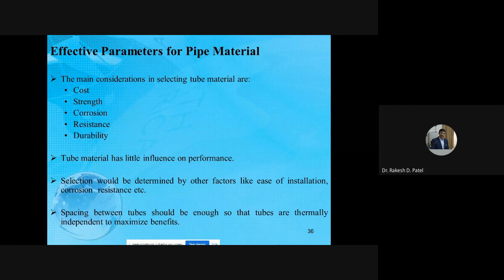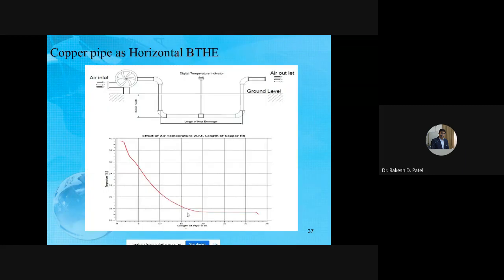In some cases, we use parallel pipes, 3 to 4 parallel pipes with a distance between two pipes of 1 to 2 meter. As well, sometimes we use a single pipe or double pipe for the analytical or experimental analysis. So in my first study, I'm using a copper pipe as a horizontal buried tube heat exchanger.